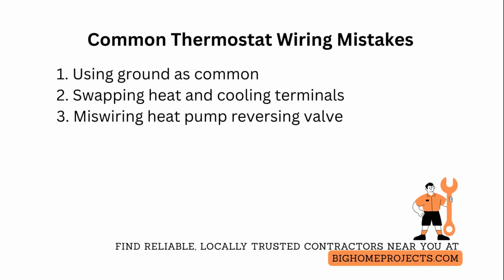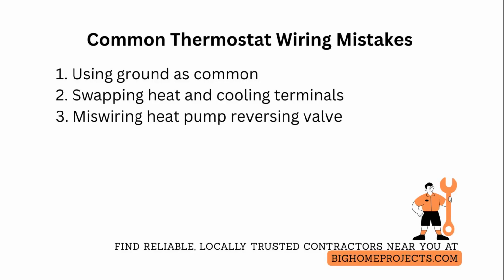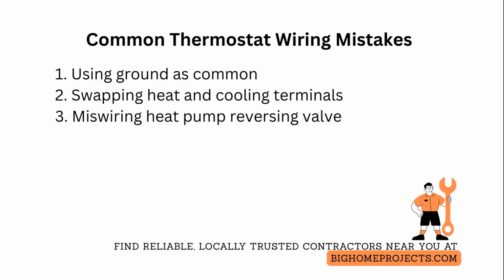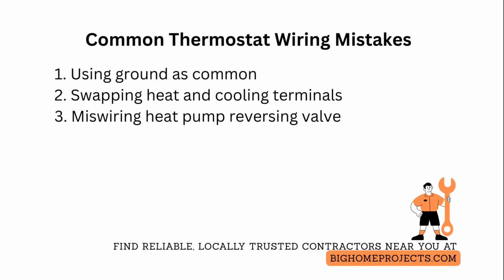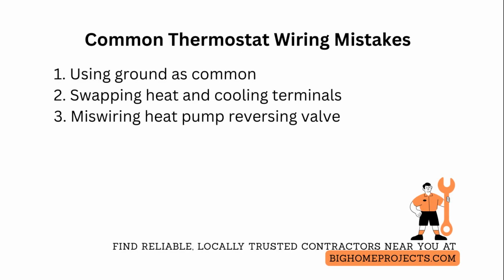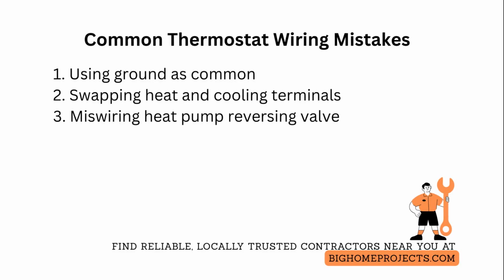The third common problem is not accounting for heat pump reversing valve wiring, so people treat a heat pump like a conventional system and either short cycle the unit or disable defrost. Correct this by identifying the O or B wire, consulting the heat pump wiring diagram, and configuring the thermostat for heat pump operation with the correct changeover polarity.